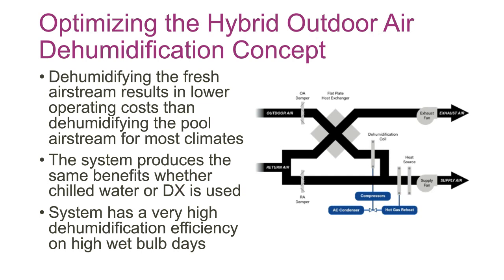This system doesn't care whether you have a DX or chilled water coil, really. It works the same way since we're not trying to heat pool water. So if you have a large university or institution that has a central plant, this system is essentially as effective with the exception of not recovering hot gas reheat energy. And it also, interestingly, has a very, very high dehumidification efficiency when you have a high wet bulb day. So if you have an 88, 78 day, the dehumidification efficiency on this is about 60%, where dehumidifying a pool airstream, you're typically down more like 45 to 50%. So it's extremely effective at doing it.